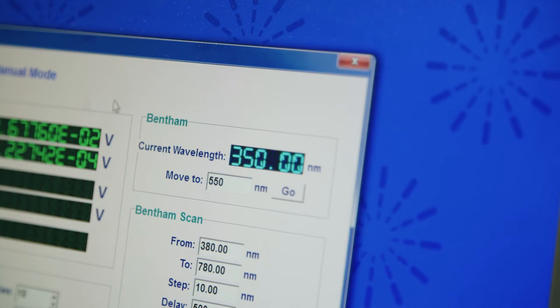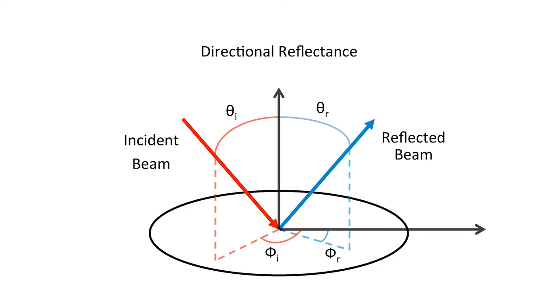The instrument you need to measure this is called a goniospectrophotometer and this is what we have at MSL. We select the wavelength of the incident light and the beam direction is fixed and we can select the angle of incidence in the sample and the angle of detection by moving the robot arm holding the sample in the position of the detector.